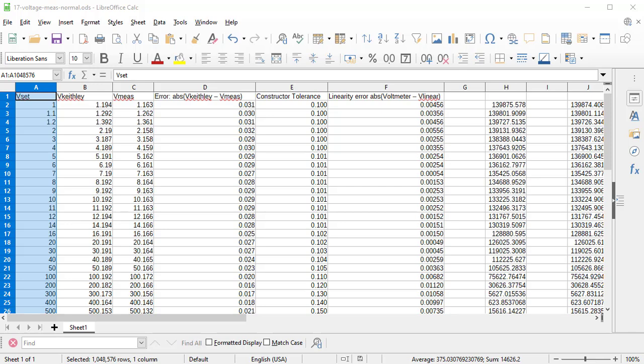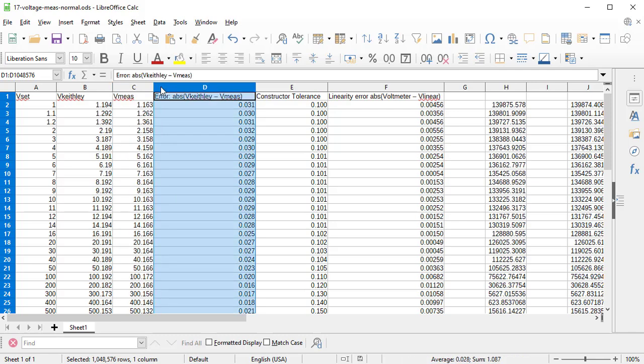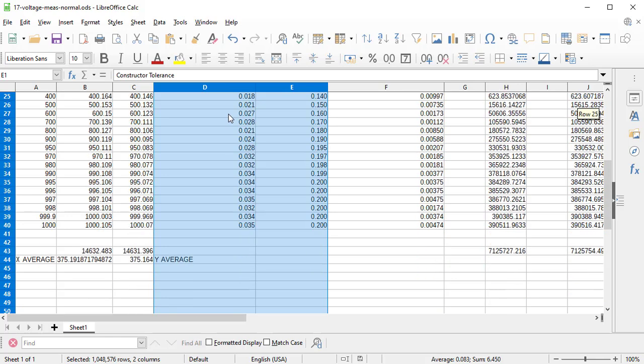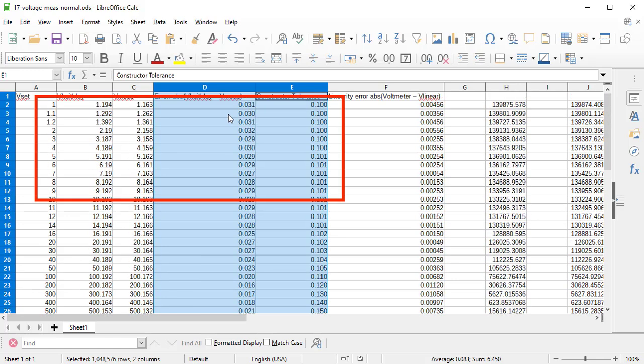The data collected during these measurements has been written to an Excel spreadsheet. The first column holds the set voltage. The second column contains the values read from the voltmeter. The third column holds the values measured by the module and read from the control software. We compare the Keithley and Iseg voltage measurements in the fourth column. We can see that these values are well below the tolerance given by the datasheet specifications. This is also true for the values below 10 volts. These values are well below the 1% range defined in the datasheet.